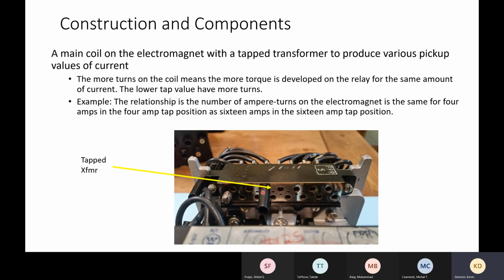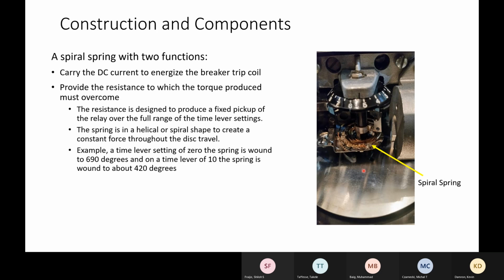As we talked about last Saturday, we've got this little screw right here, and you just unscrew it, and it can go in any of these holes. So that becomes your pickup value. So that's pickup in secondary. Take your current transformer ratio and multiply it by whatever your pickup is, and that's how much it's set to in primary amps. There's also this spiral, it's a real thin piece of copper wire. What it's actually used for is it brings DC up to this contact right here. So this is a movable contact, and it also provides some resistance.